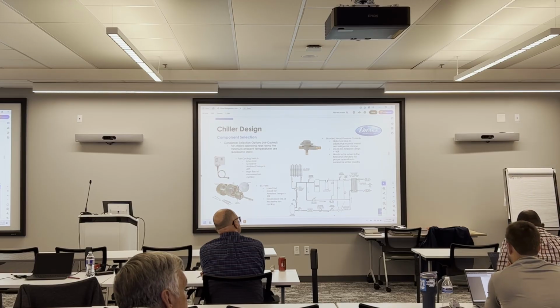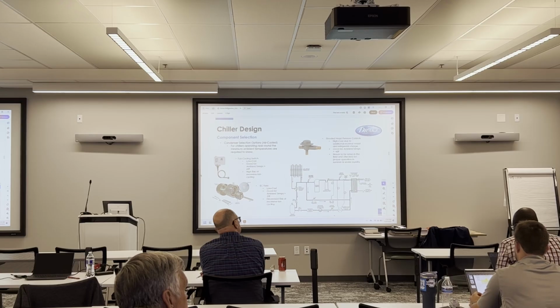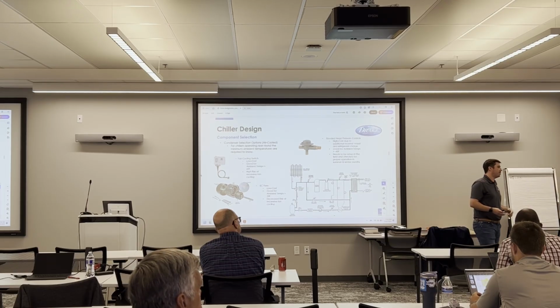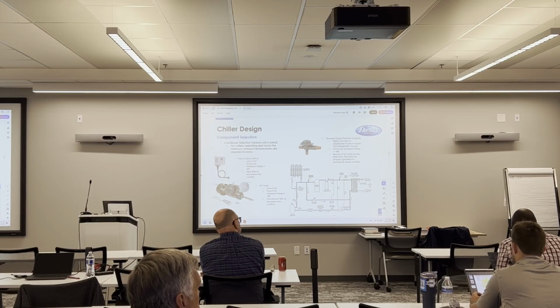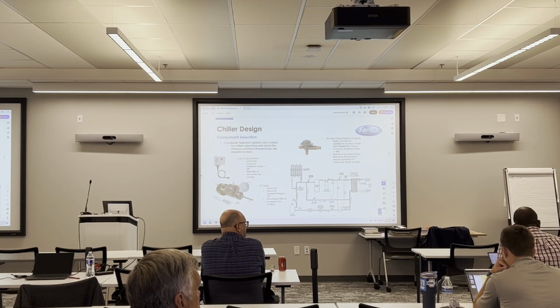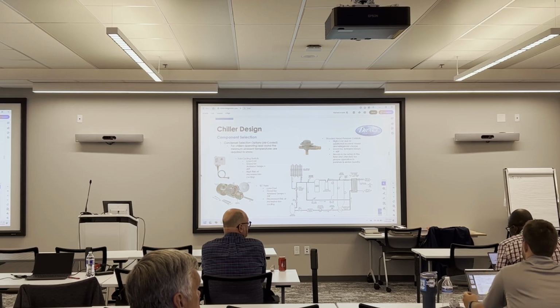Yeah, I would say. If you wanted to use a bigger fan motor, you can get away with using a smaller condenser, obviously, because you can increase your CFMs and decrease the size of the coil you would need. But the condenser I had on the previous example is made by another manufacturer, so we kind of work with what they got. But we have done jobs where I had to put a chiller on the back of a truck. I think it was for the University of Oklahoma. They're actually chasing tornadoes. So they needed a lot of capacity, but they didn't have a lot of space because the thing had to fit on a flatbed truck. So we ended up getting a 10 horsepower fan motor with a smaller condenser coil. That thing was loud as hell, but it did the job. We threw a variable frequency drive on the motor just to modulate it, depending on the ambient air. But yeah, it's pretty cool.